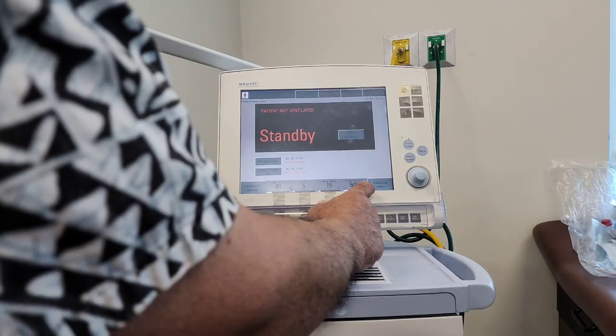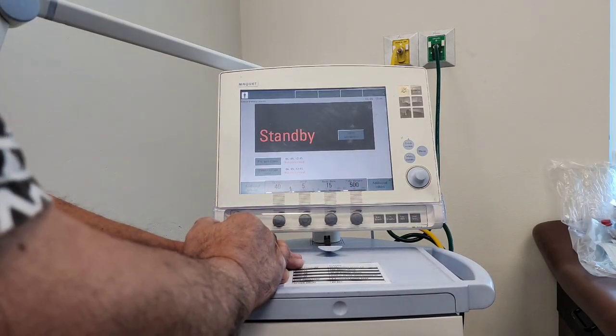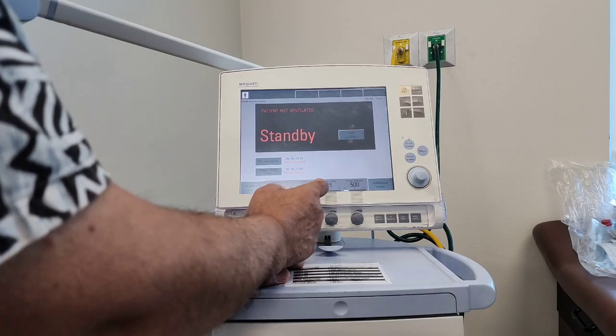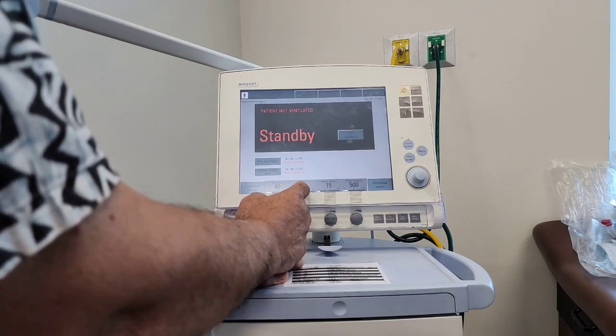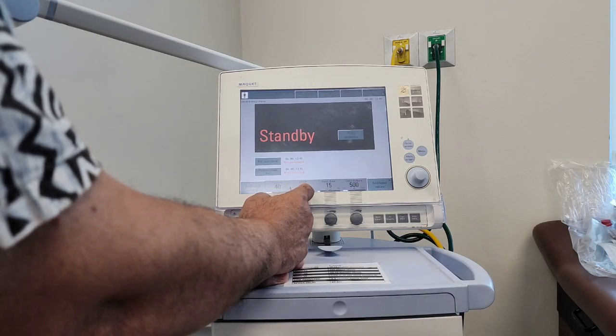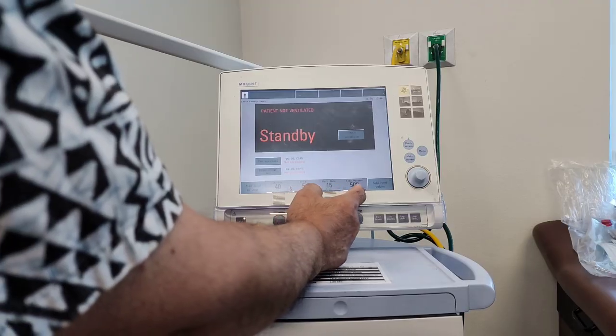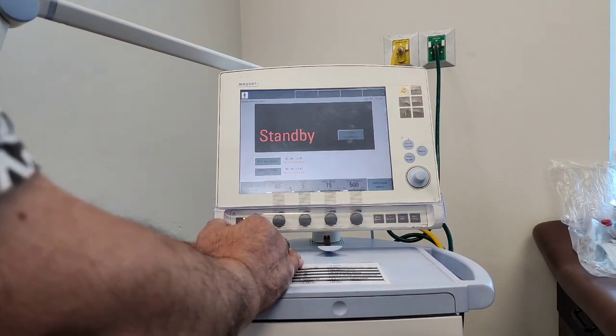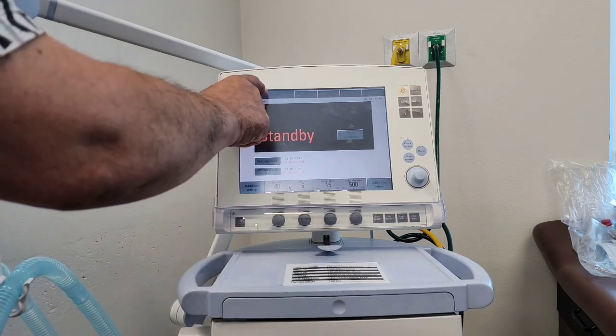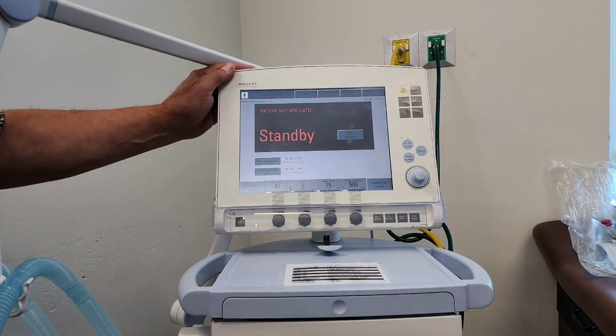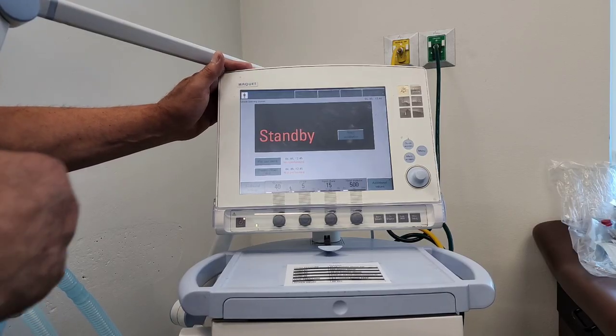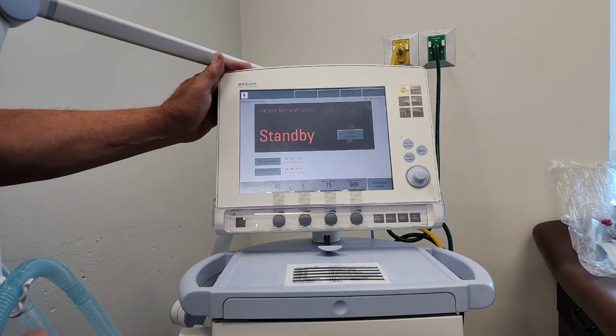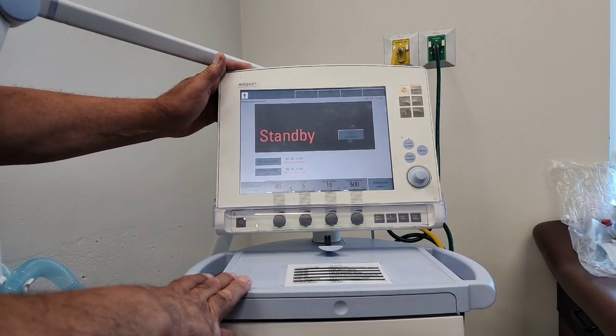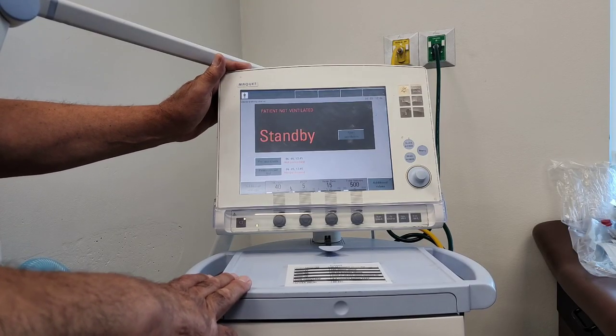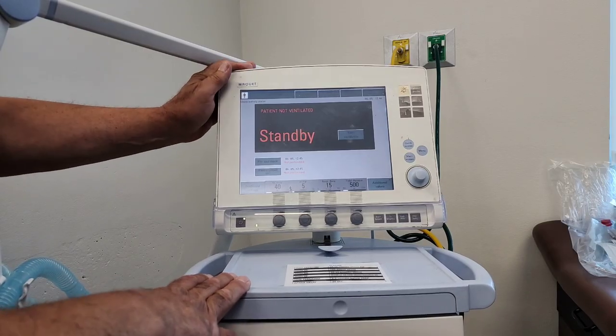It gives you some real basic numbers here. You have oxygen concentration, you have PEEP, which is positive end expiratory pressure. You have a respiratory rate, and you have tidal volume, okay? Right now, if we look up on top, it is set up to be volume control. So we're going to be delivering a set volume at 15 breaths per minute, okay?